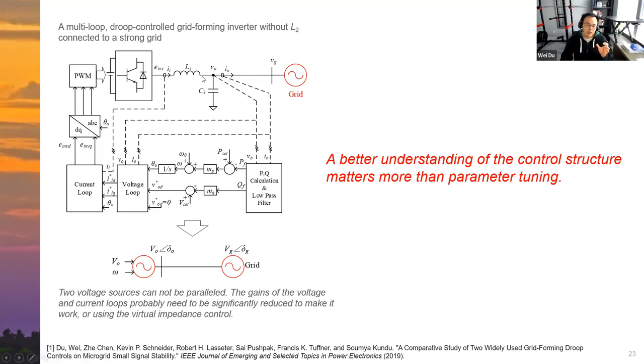But if you use the CERTS droop control, the L2 is in the circuit, so it can still work. So I think that's purely decided by how you design your controller. What I'm saying is that a better understanding of the control structure matters more than parameter tuning. So before you start to tune your parameters, try to see if you understand the control structure of this grid forming control better. Then this is the second section.